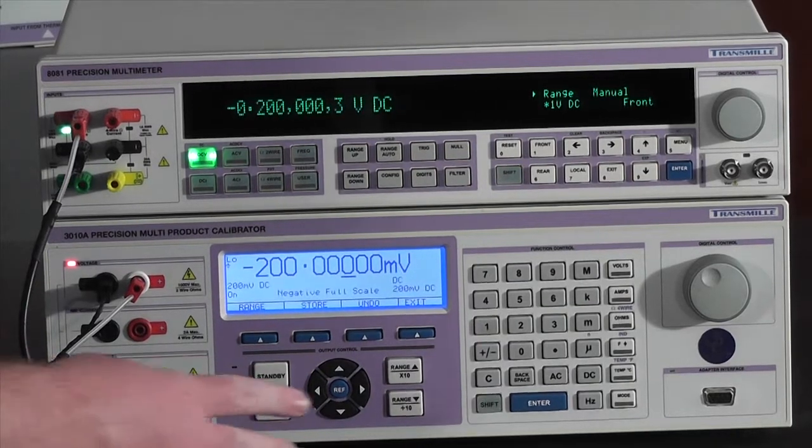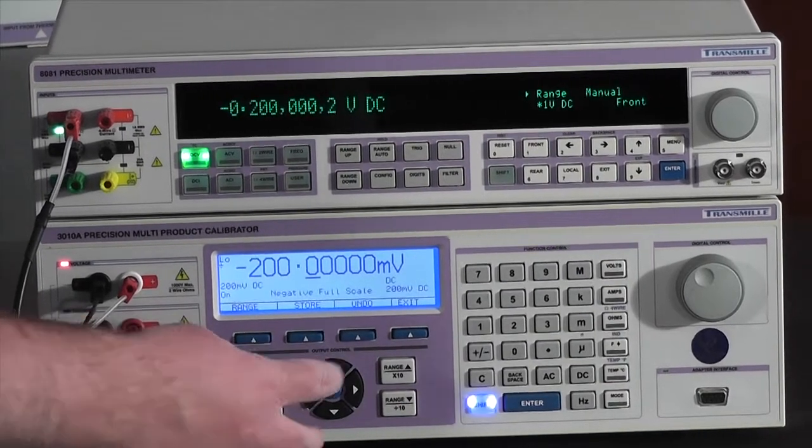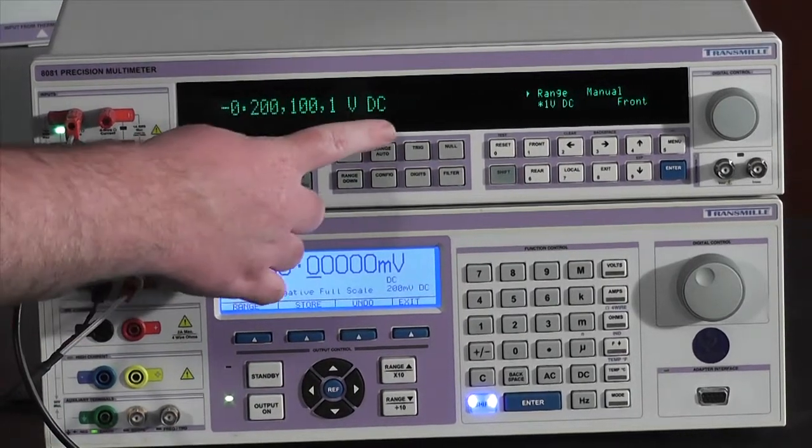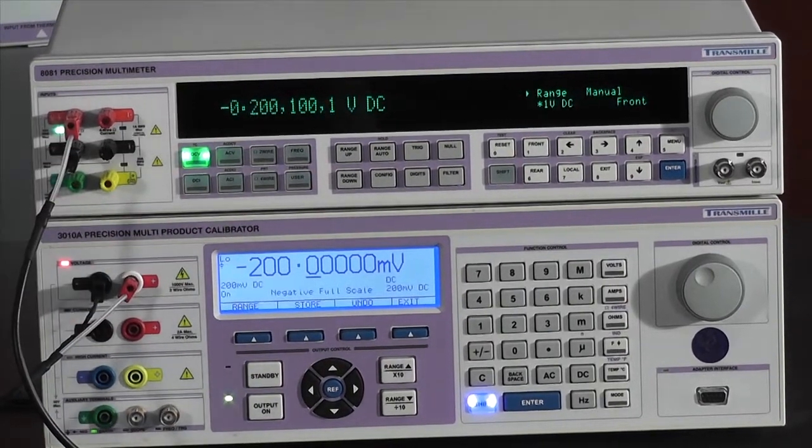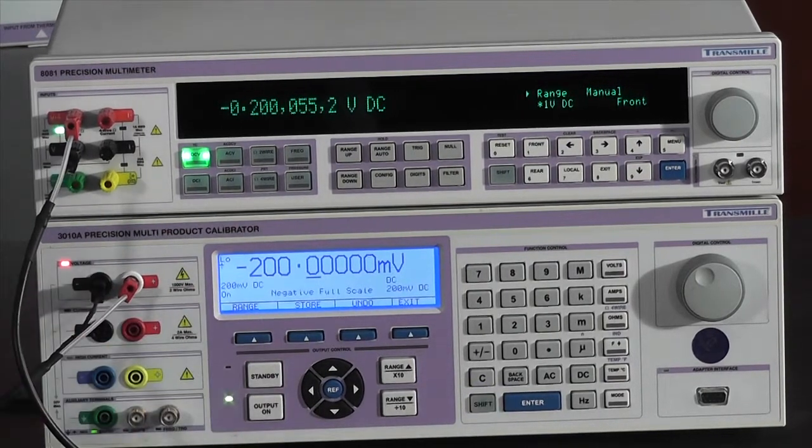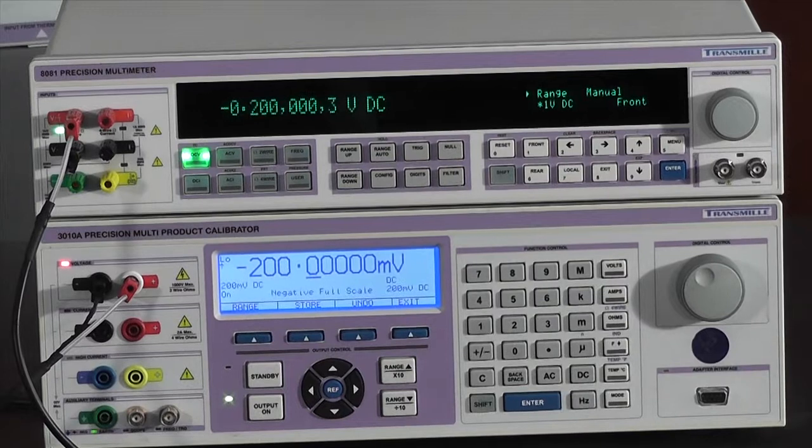If in the event that you make an adjustment that you do not want to keep, for example, I have adjusted this far too far, you can simply press undo and it will put the calibrator back to the previous output.